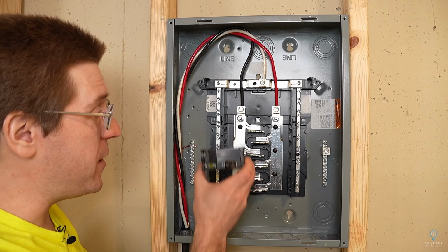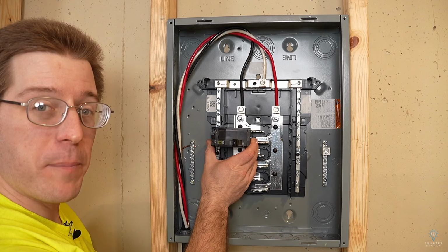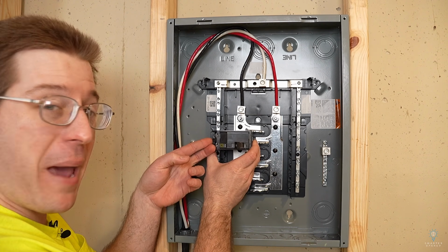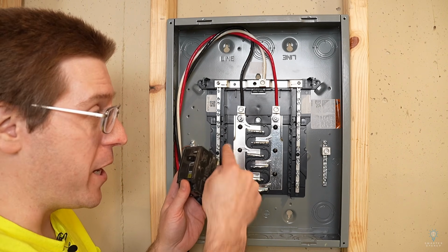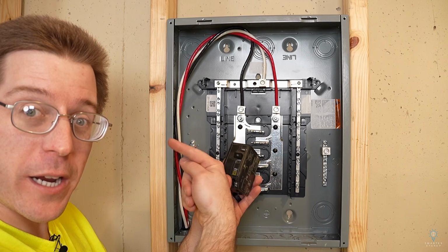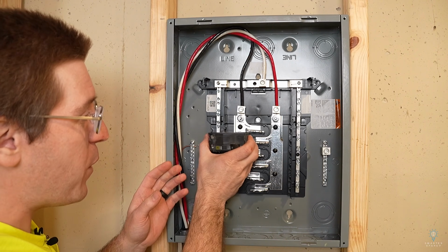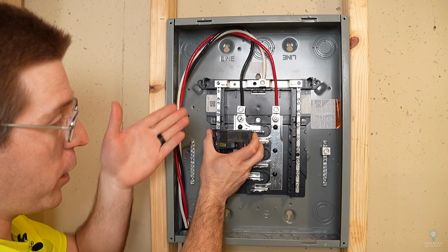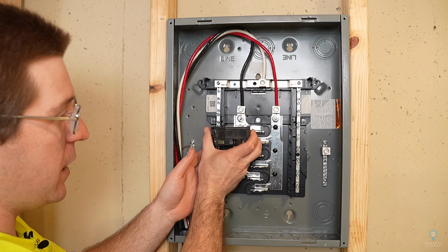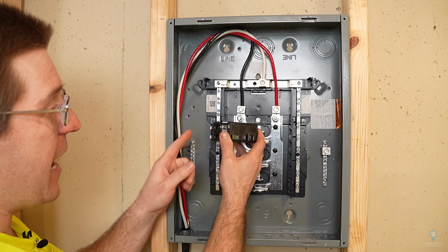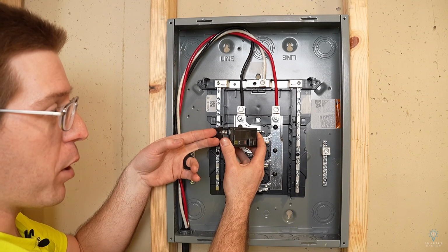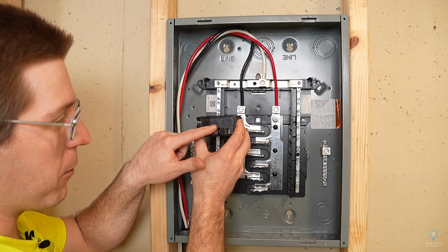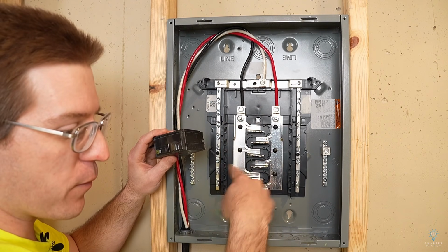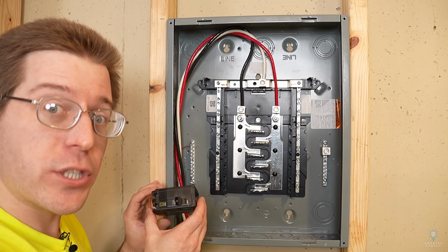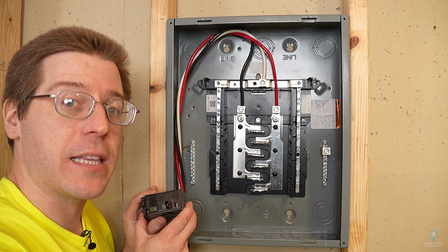Another option would be to install a breaker in the panel like this, and you can actually backfeed it. This isn't the right style breaker for this panel. This is actually going to be the breaker we're going to use in the main panel. But if we had a 60 amp 2-pole breaker for this panel, we could install it right here and backfeed through this breaker, and this would be basically our main breaker for this panel. And that's fine. You're actually allowed to backfeed breakers like that per code.